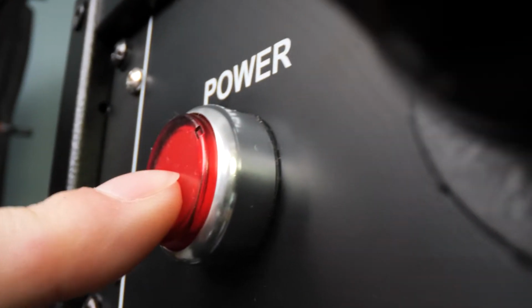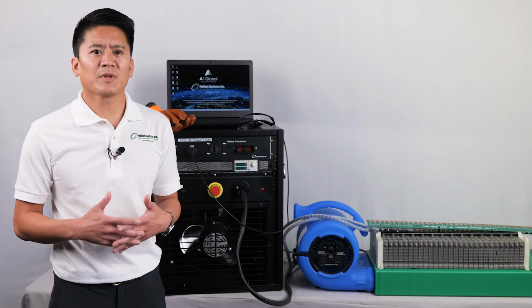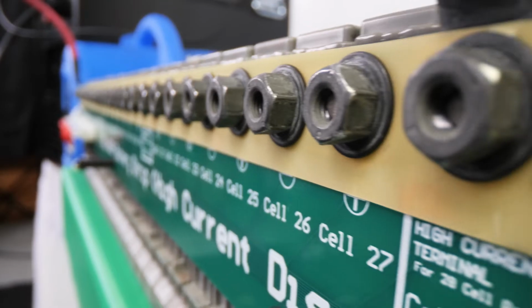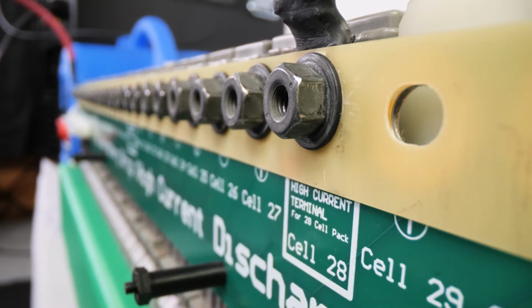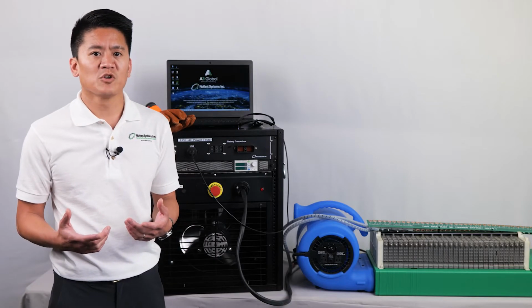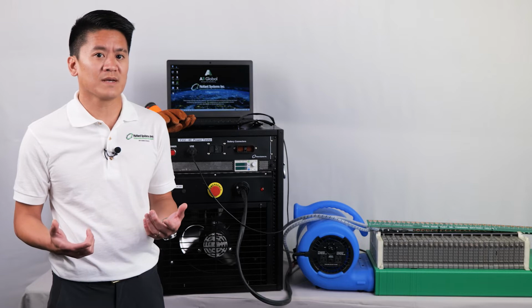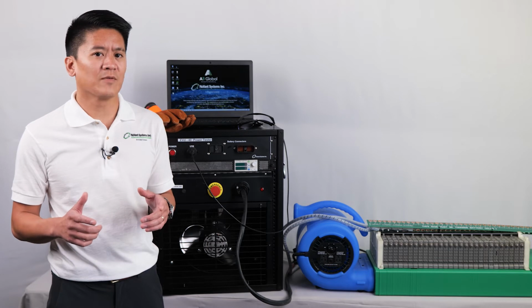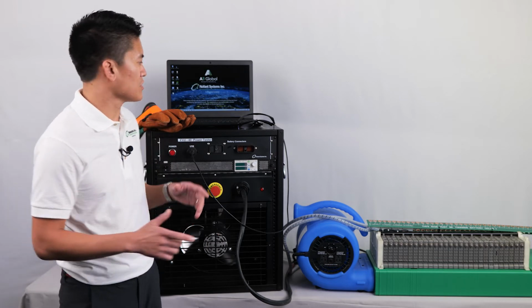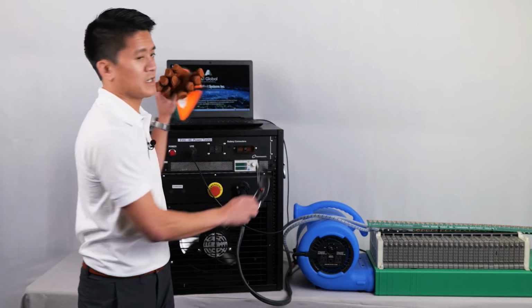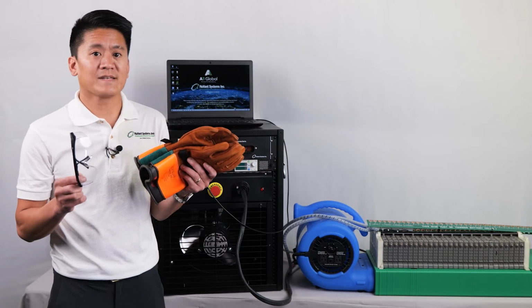The EVd40 is intended to power test modules post reconditioning. After assembling a set of modules, whether it's 28 modules for a Toyota Prius or 34 for a Toyota Camry, you should run a power test or load test with EVd40. Please watch the EVc30 instructional video to learn how to use our pack loader software to choose a balanced set of modules. Since the power test requires high voltage and high current, please use all required safety equipment, such as insulating gloves and safety glasses.